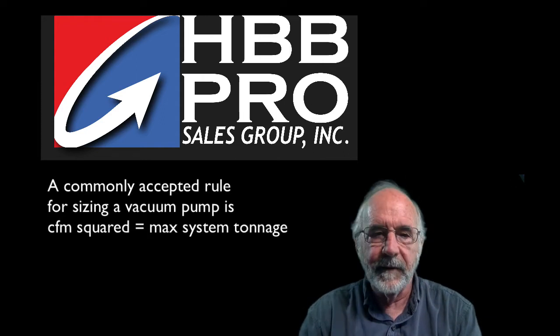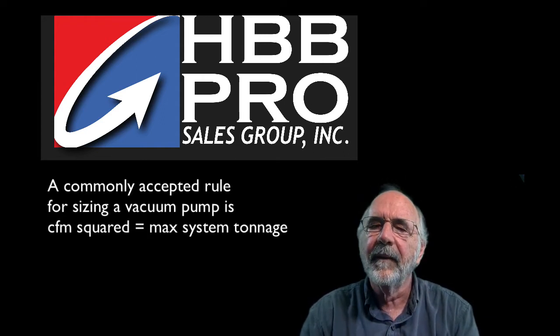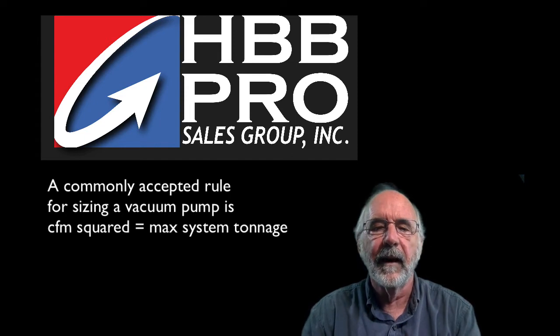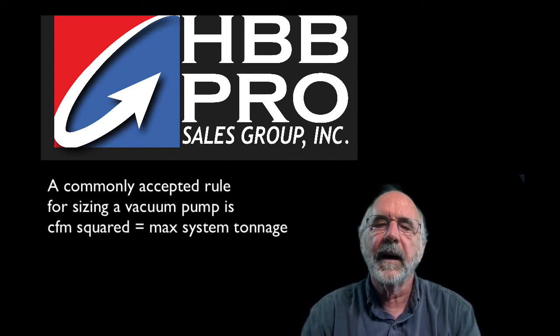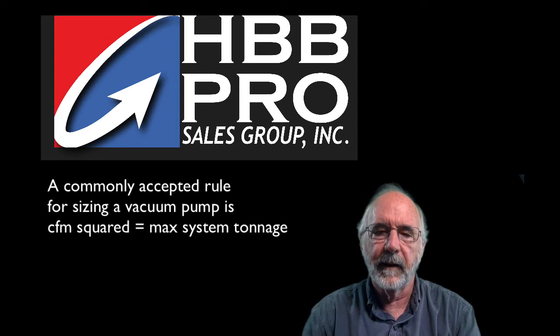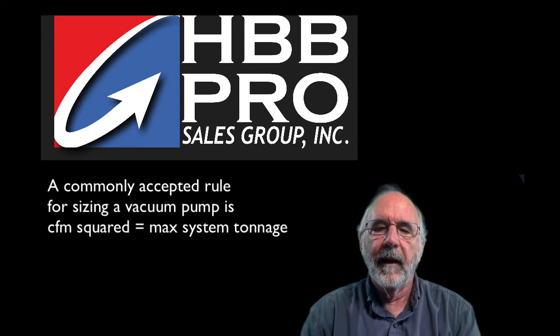I've seen several references to sizing a vacuum pump by taking the square of the CFM rating, which then suggests the maximum tonnage of the equipment that that size pump will handle.